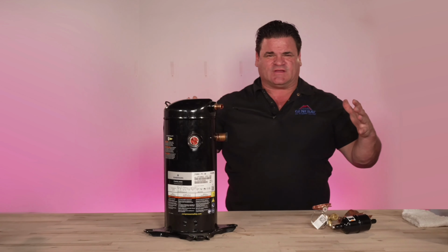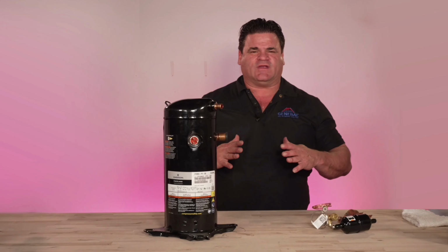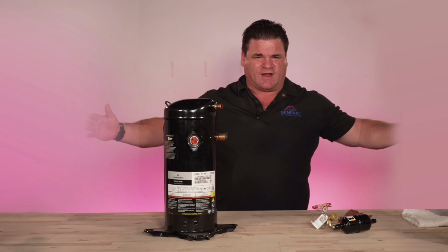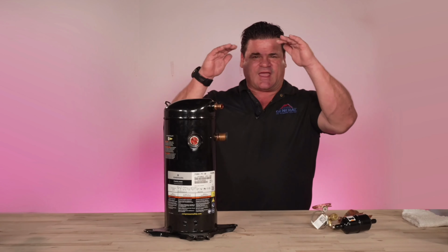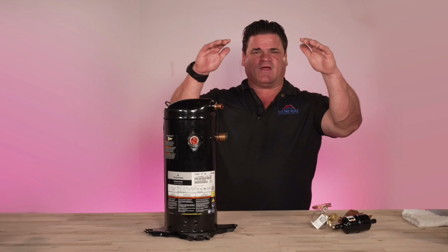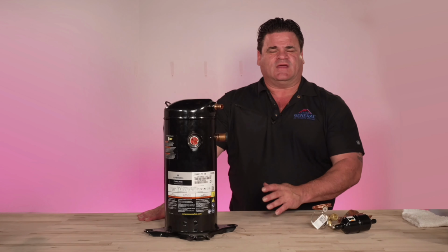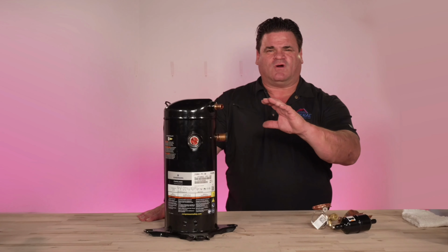And then that condenser that sits around this compressor is where the refrigerant's going to go through. And it's going to eject the heat, essentially. That's why that fan is there, to pull air in across those coils to the center and eject out the top. So that hot air you feel is the hot air coming out of your home. Now, in that process of traveling through that condenser coil, it's going to turn into a liquid, all right? And then it's going to travel on to the coil.